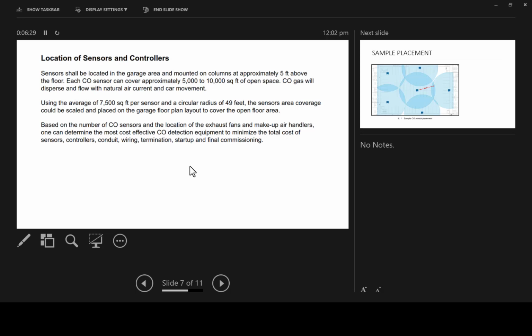So like we discussed, these fans will not run continuously at high CFM. They will run only when the CO level is detected high. So you need a three-speed fan or VFD drive fan to work like this. We will discuss the CO sensor. First, we will discuss how to calculate the air. You need that much air to be exhausted.